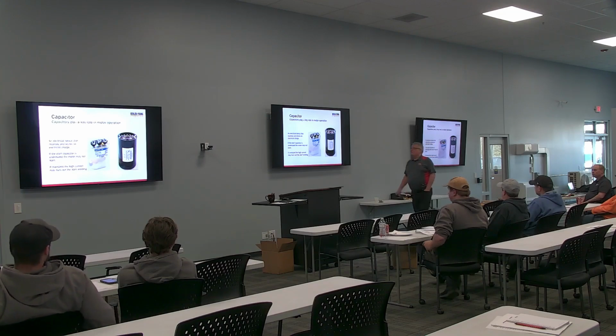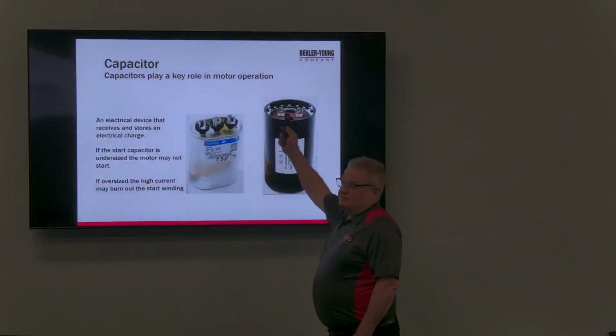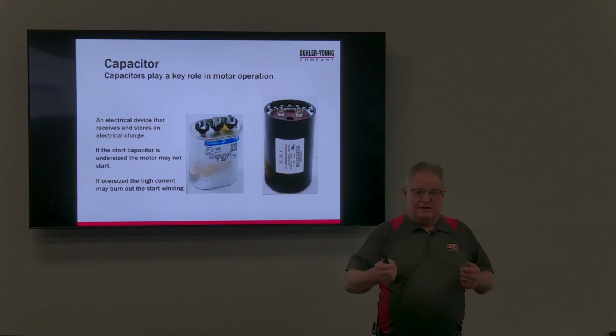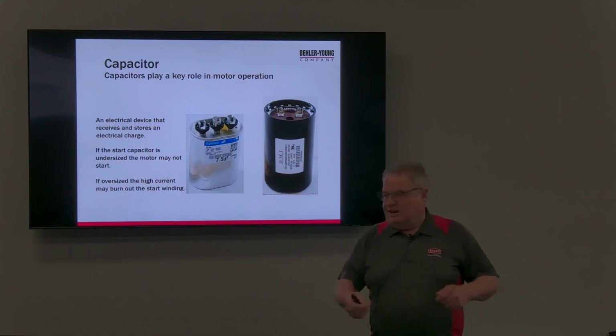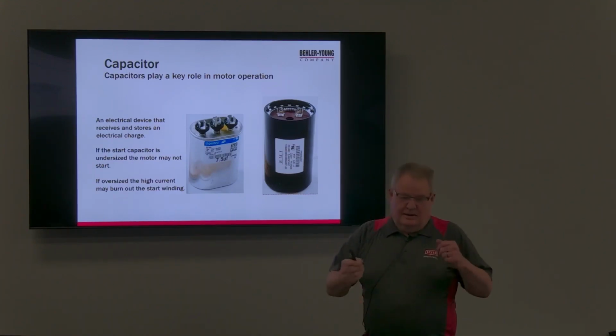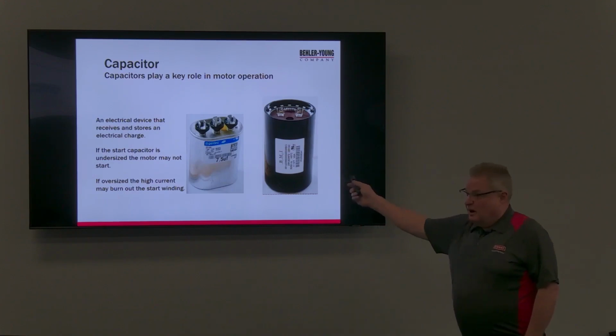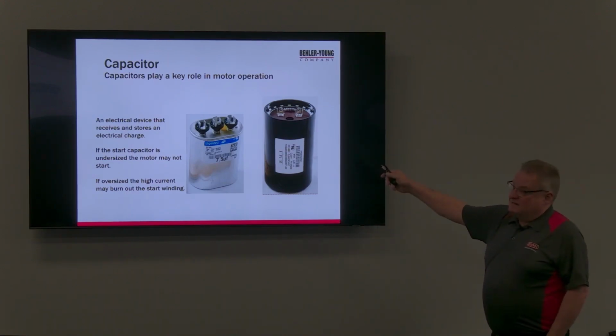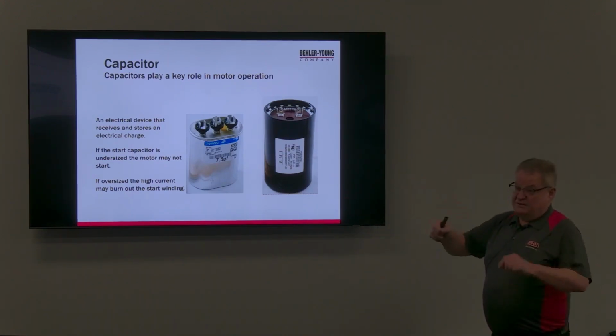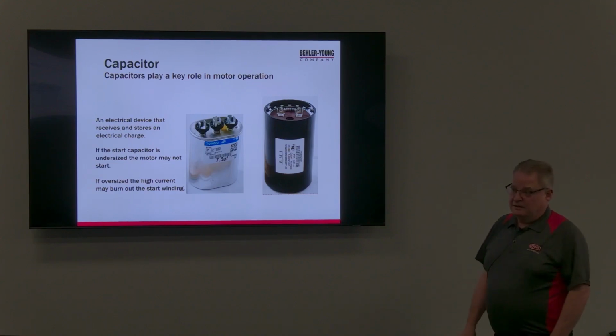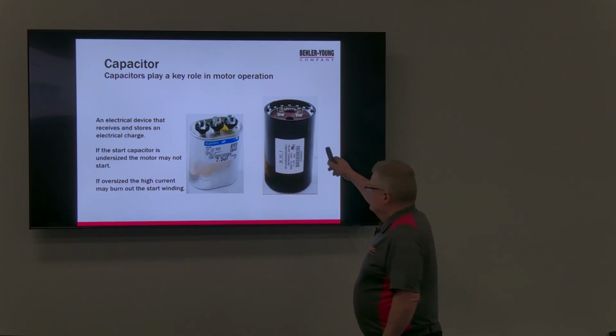So, good point. Or like I said, you can just put your DC voltmeter on and check for voltage and make sure they're dead. Nowadays we all have meters that have microfarads on them, so to test a capacitor you have to cut that bleed resistor off. If you have to cut it off to test it, we sell a bleed resistor with spade connectors, so put it back on there, because that's just there to bleed it down.